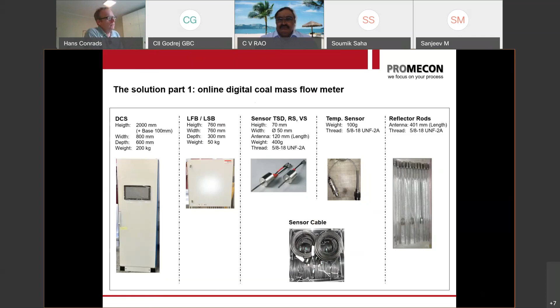The system works similarly to the airflow system. We measure velocity by cross-correlation, but we also measure coal concentration using a microwave resonance technique, a patented method already applied to thousands of burners. This lets you see the coal concentration in each pipe. Coal concentration multiplied by velocity gives you coal mass flow in kilograms per second for each pipe of the mill.